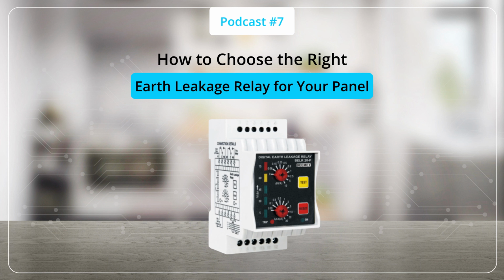Another consideration is the auxiliary supply voltage. The relay's operating voltage should match the available site supply. The CBCT size is also important. The CBCT window must be large enough to accommodate the cable bundle passing through it. Many users also evaluate advanced features such as Modbus communication, alarms, diagnostics, and event logs. These features can significantly improve monitoring and predictive maintenance capabilities. Finally, consideration should be given to mounting requirements and environmental ratings, including DIN rail compatibility and protection ratings suitable for industrial environments.